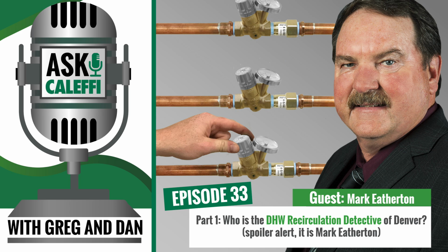And I said, are there check valves on the cold and hot water supply? And he said, I don't think so. And I said, you just discovered your cross connection. I said, have them close at least the hot or the cold water valve on every one of those valves and see if hot water is restored at the showers. And I have not heard from him. So my assumption is that's where it was, and that took care of it, because if it hadn't, he'd have been calling me back going, well, no, that didn't work. What's the next thing?